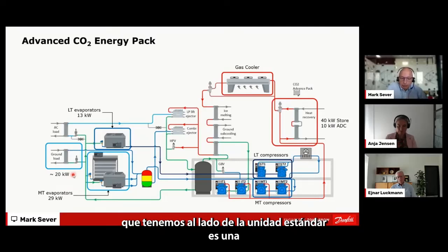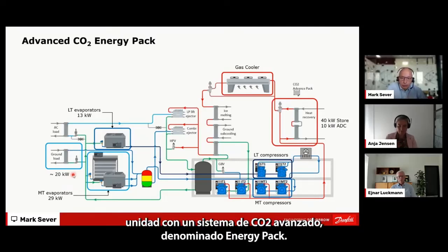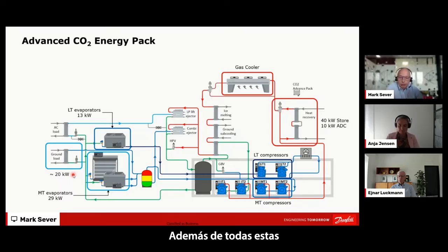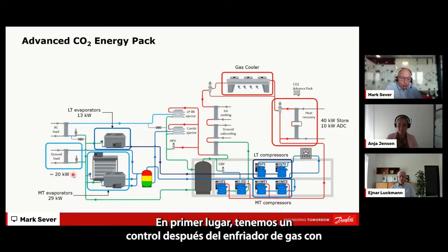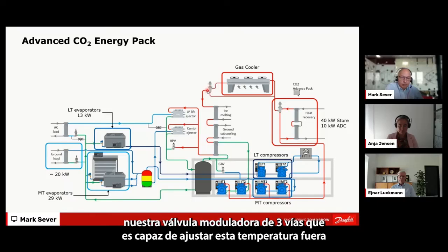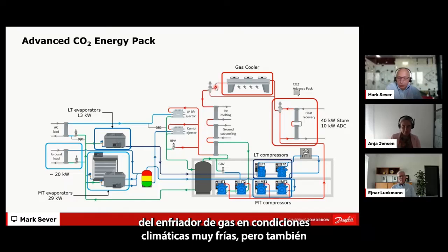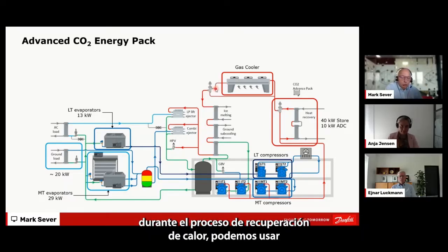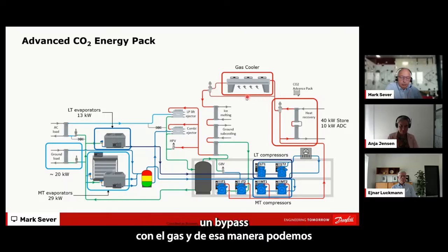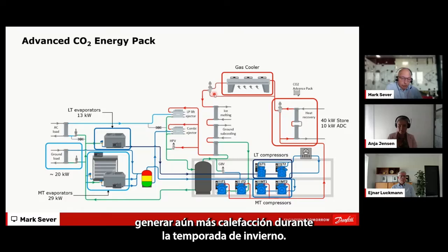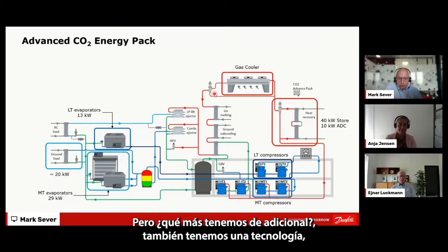Next to this standard unit, we have the advanced CO2 energy pack. Beside all the units we discussed before, we have something additional. First of all, we have control after the gas cooler with our modulating three-way valve, which is capable of tuning the temperature out of the gas cooler in very cold climate conditions. Also during the heat recovery process, we can completely bypass the gas cooler and in that way create even more heating during the winter season.